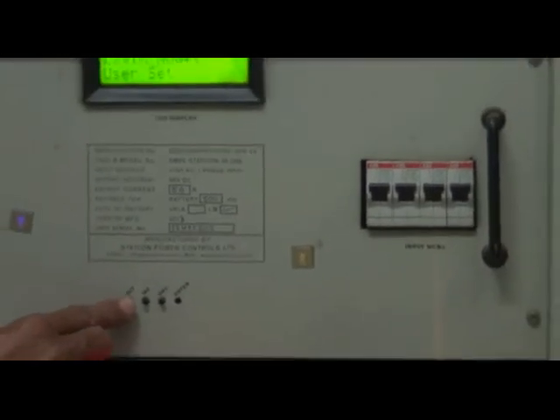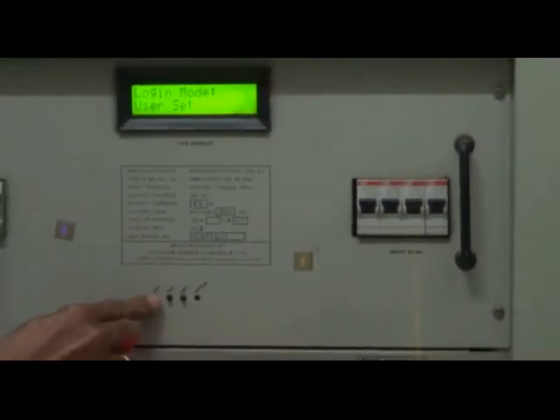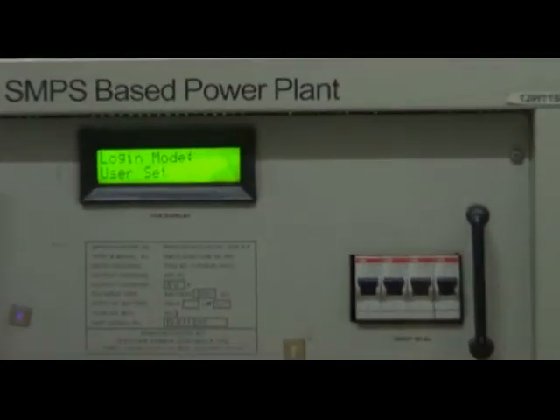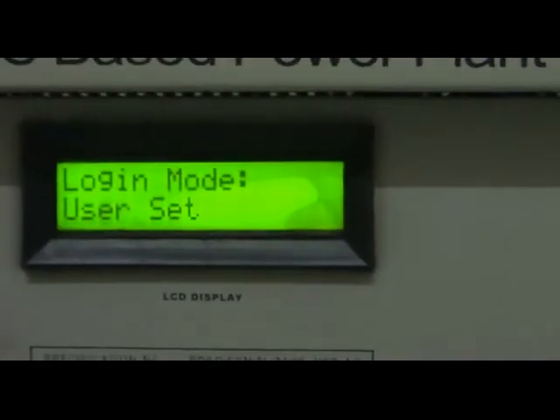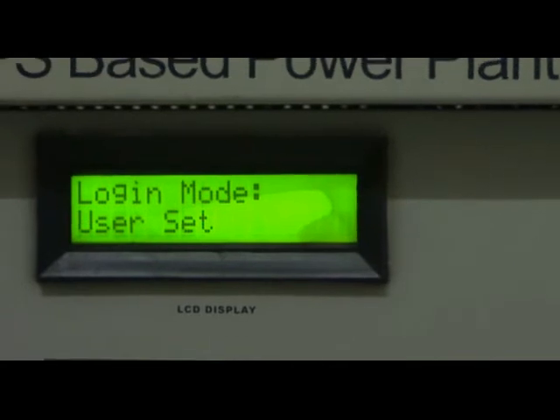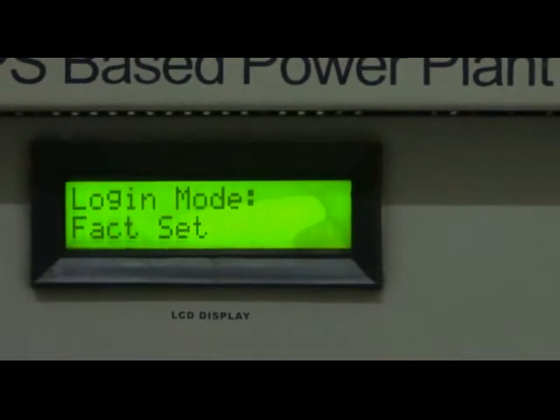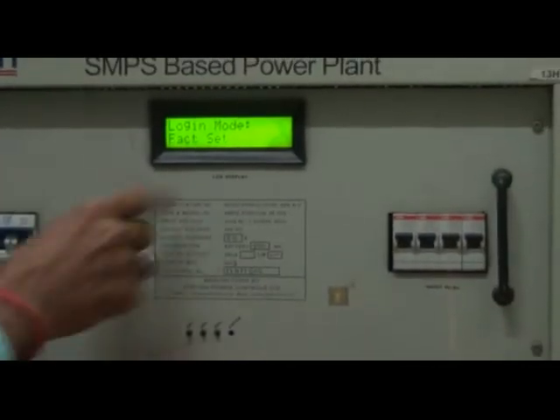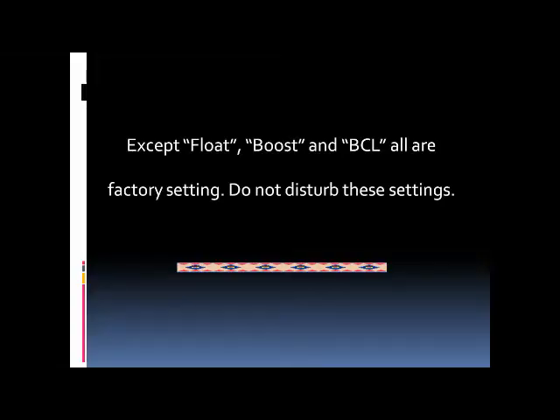To see the parameter values, press set for 3 seconds. The system will display login user set. Press set again to choose fact set. Except float, boost and BCL, all are factory setting. Do not disturb these settings.